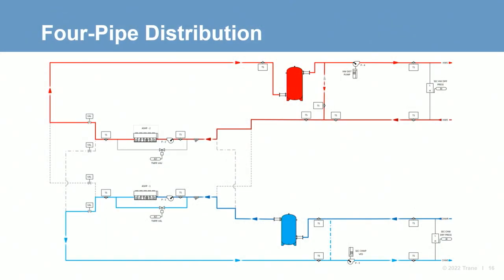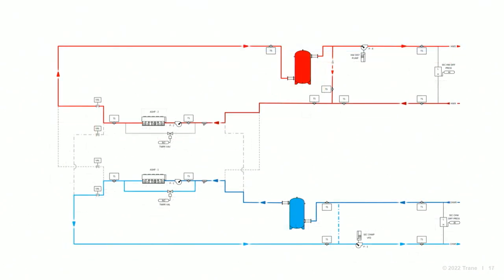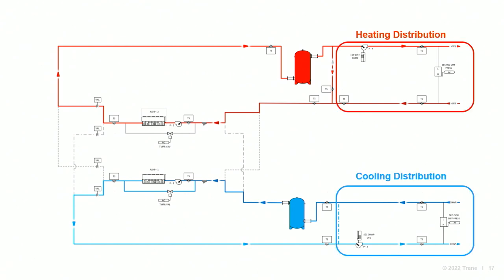Next, we want to talk about the systems these air-to-water heat pumps will be applied in. For today's discussion, we'll be focusing in on a dual-feed production system with four-pipe distribution. While other system configurations are possible and will not be unusual, this one provides excellent flexibility and simplicity of design and control. First, we'll look at the distribution loops. Four-pipe distribution allows for heating and cooling of the building zones simultaneously, meaning any zone has the ability to receive chilled water or hot water as needed throughout the year. Typically, these loops would be pumped using variable flow.